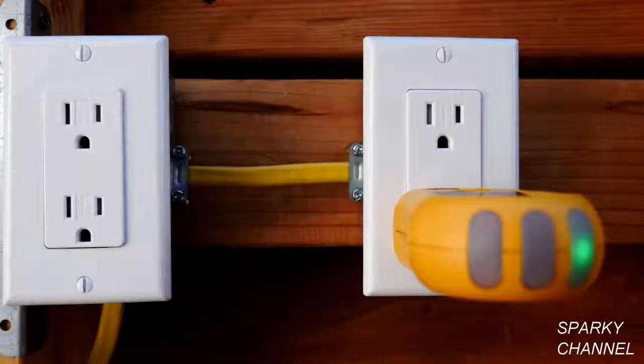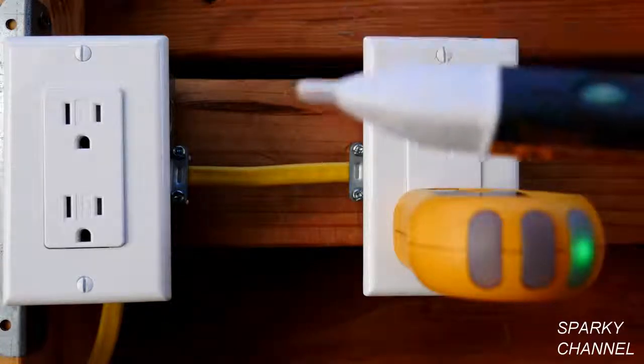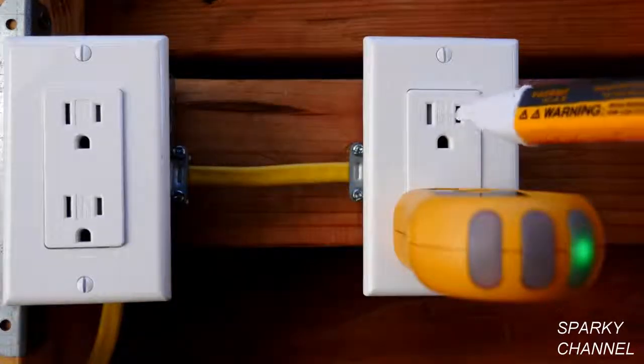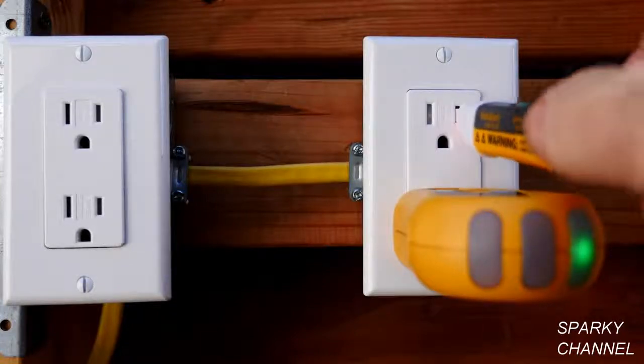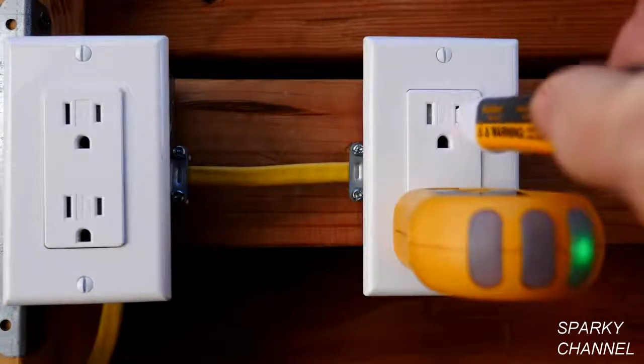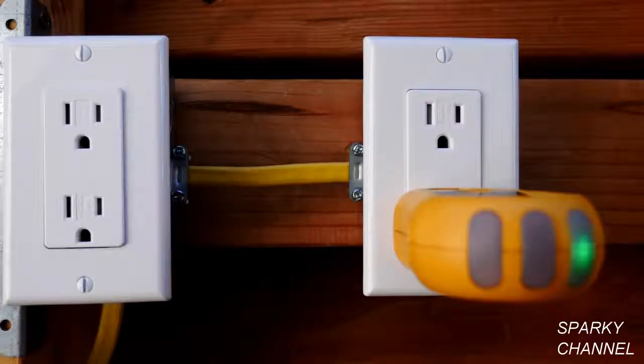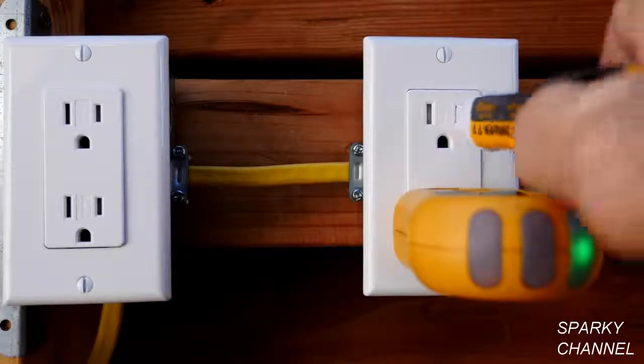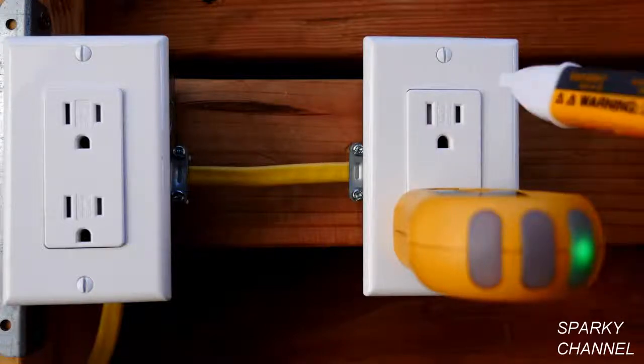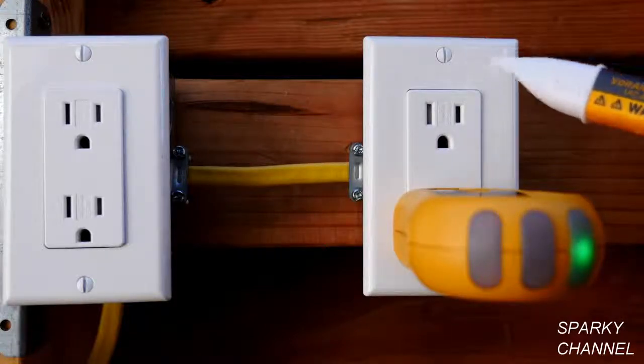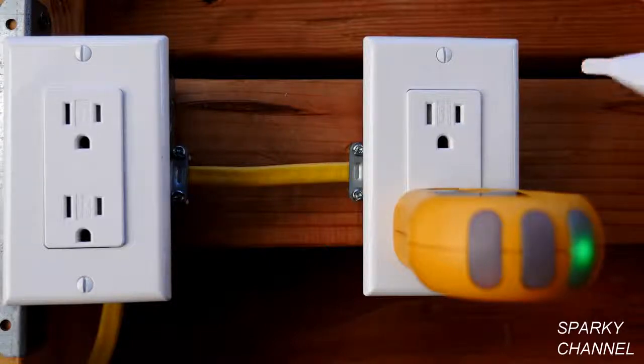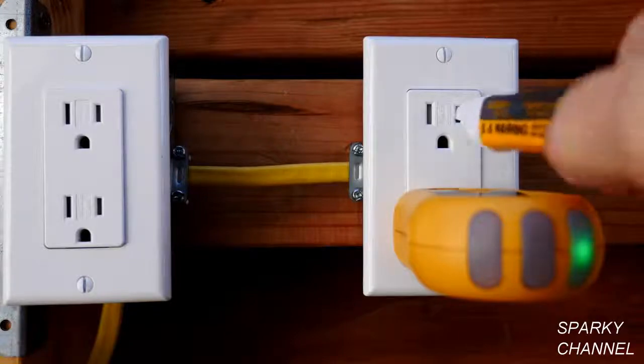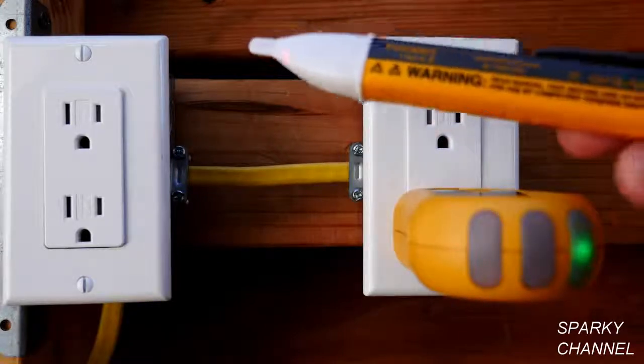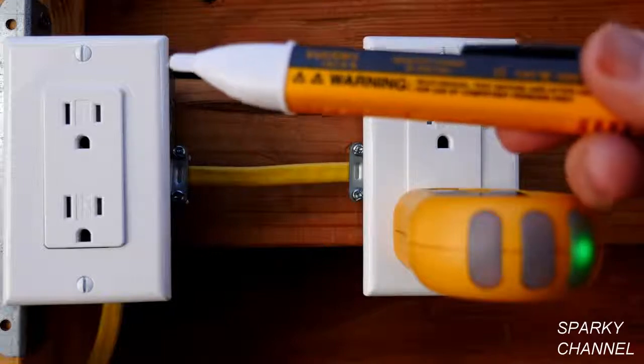The first thing I'm going to do is turn off the circuit breaker. But before I turn off the circuit breaker, I'm going to take this opportunity to test my voltage detector. See, it works just fine. You put it in the hot slot right here, and that does tell us something. It tells us that we do have electricity coming to this receptacle. So it's pretty much agreeing with the outlet tester, because the tester says open neutral. It doesn't say anything about the hot wire being a problem. That shows that our voltage detector is working properly.